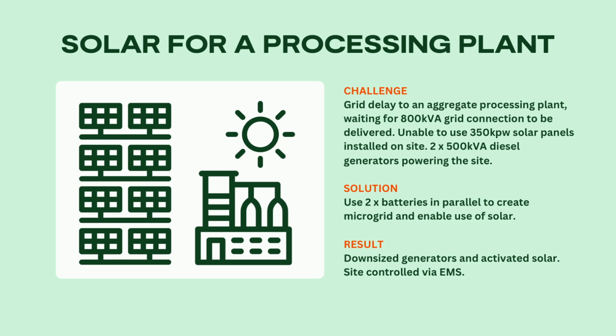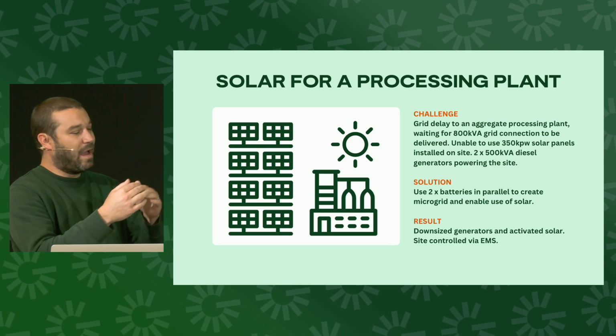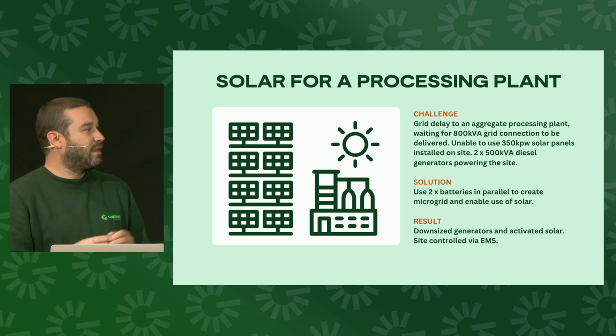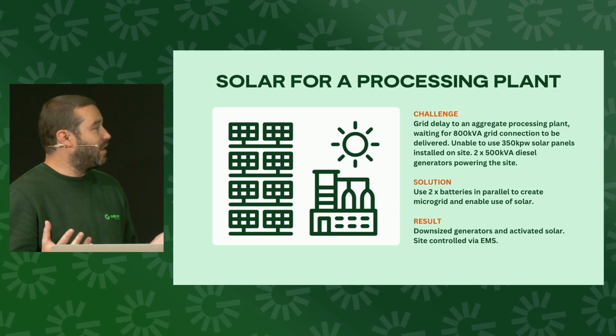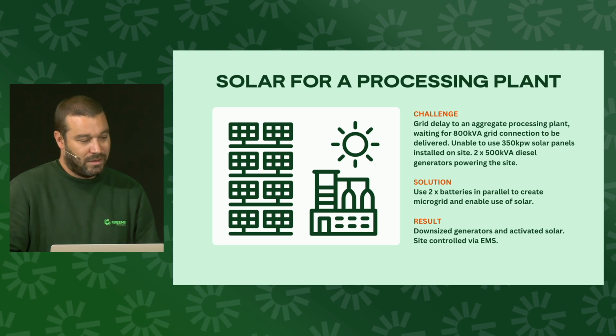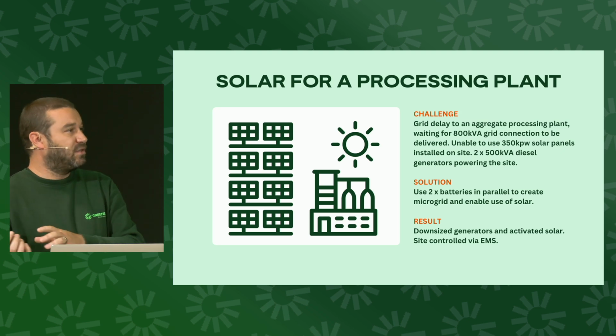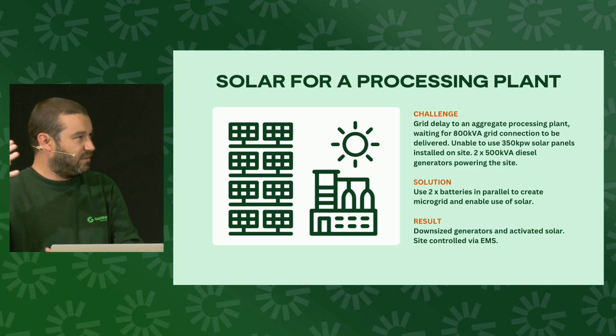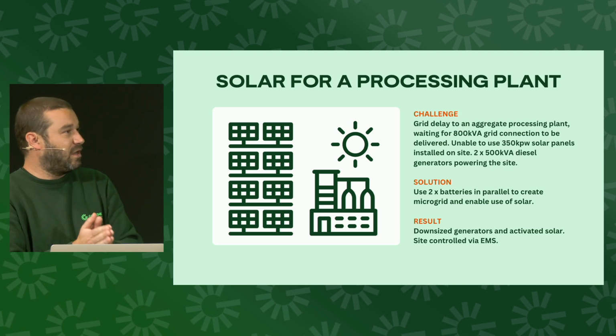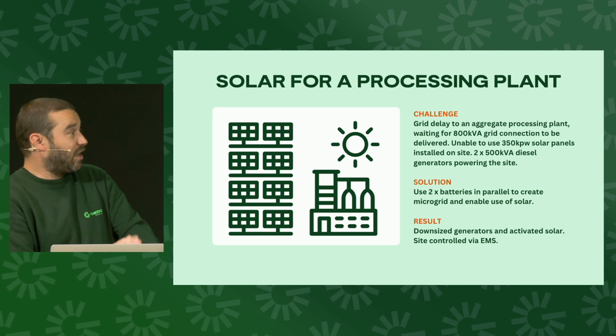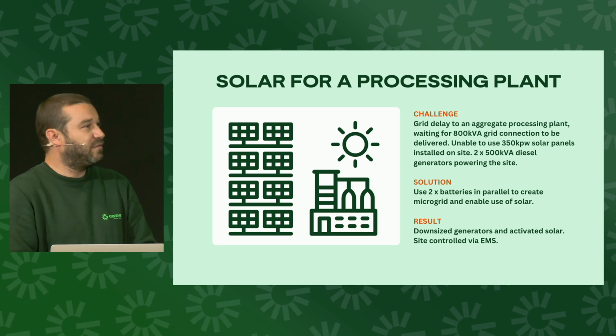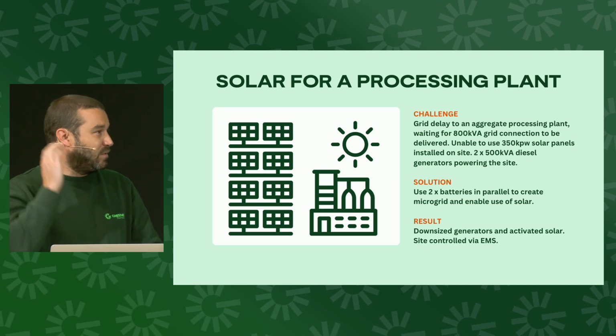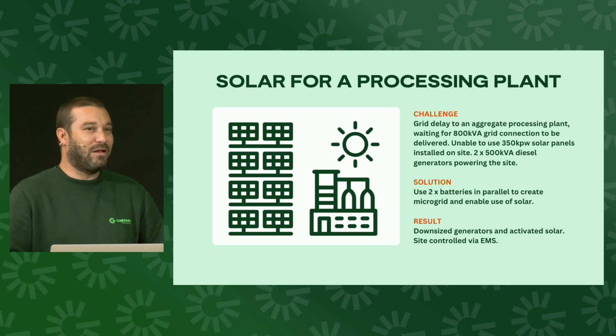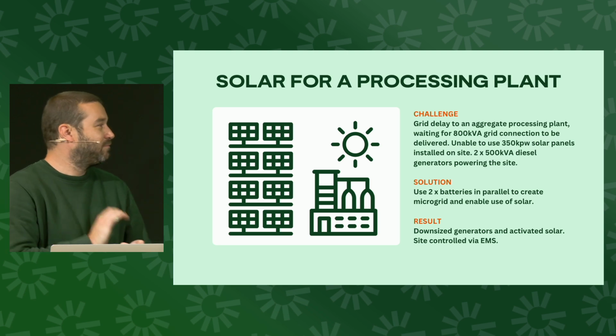The reason being, if the solar array is pushing more power than the site load is consuming, then there's nowhere left for that excess energy to go. The only way it could go would be back to the generators, which would cause the alternators to overheat. And of course, most generators do have a protection function that would cause them to shut down if they detect power being fed back in, because eventually that alternator would melt, catch fire, and explode. It's designed to produce power, not absorb.